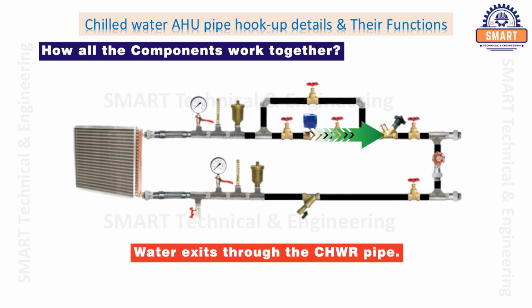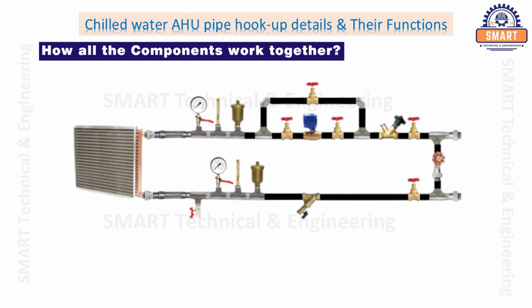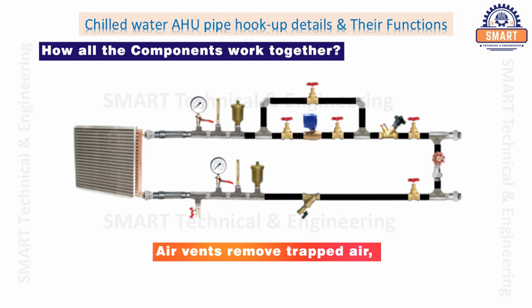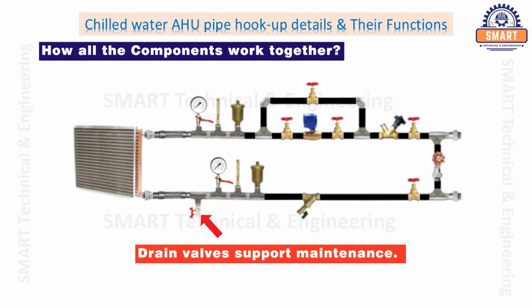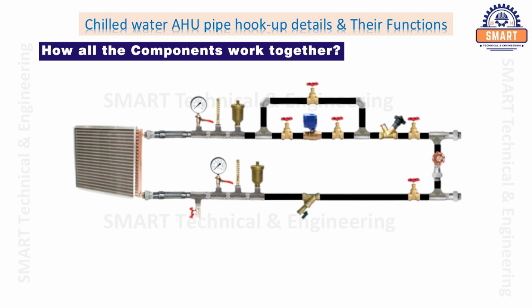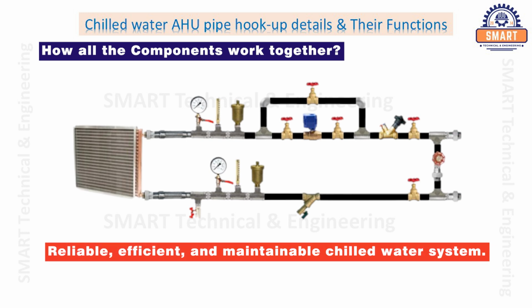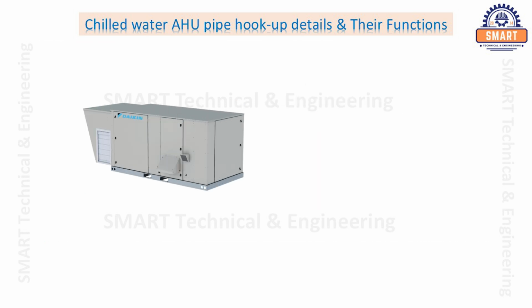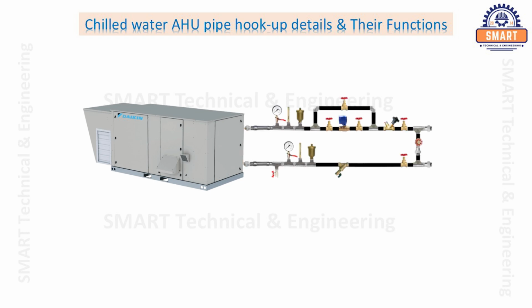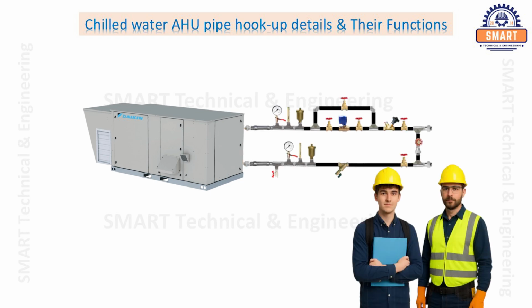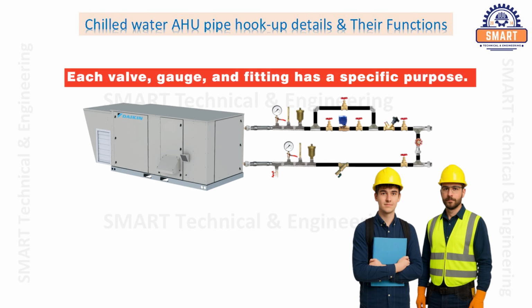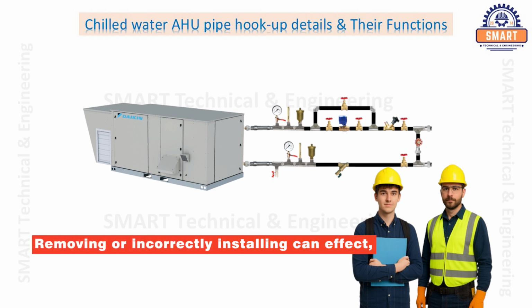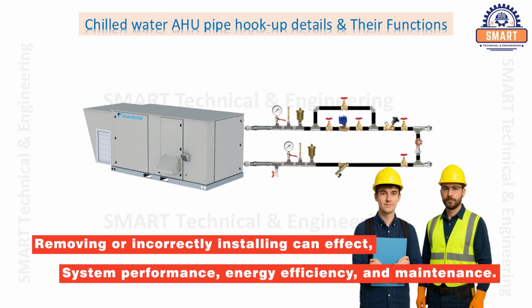Water exits through the chilled water return pipe. Air vents remove trapped air, while drain valves support maintenance. Together, these components create a reliable, efficient, and maintainable chilled water system. Understanding the chilled water AHU pipe hookup is one of the most valuable skills for HVAC engineers and technicians. Each valve, gauge, and fitting has a specific purpose. Removing or incorrectly installing just one component can affect system performance, energy efficiency, and maintenance.